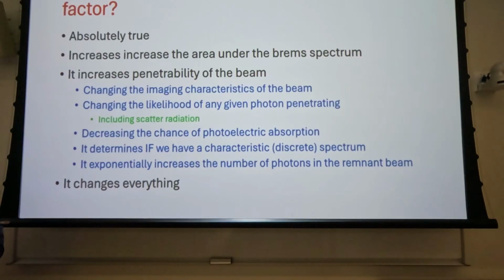Nothing. Did nothing, right? It does at the image receptor, but at the tube housing, there's no change, right? So, you know, 2 mAs is 2 mAs. At the image receptor, there is a significant change. It's not as significant as what a change in kVp would be, but that's SID. So let's say you change your mAs, either mA or time, by a factor of 2. So you either increase or decrease one of those factors by a factor of 2. How much of a change in emission do you have?